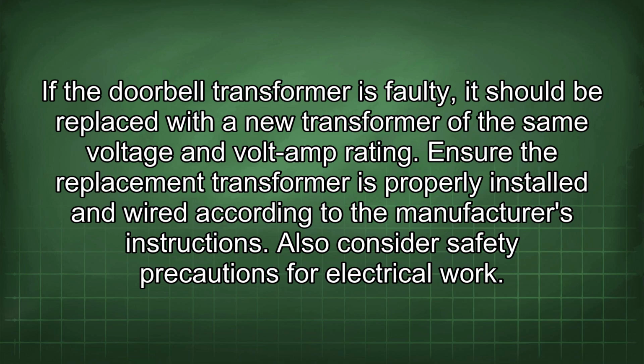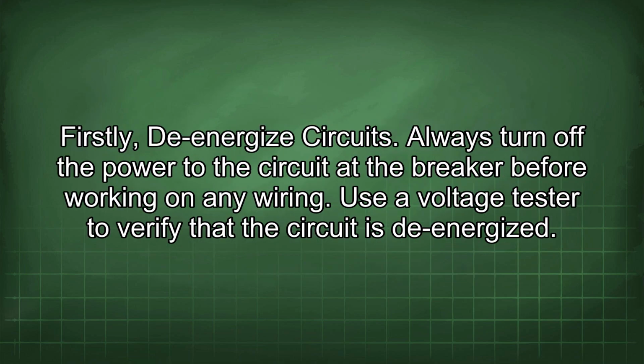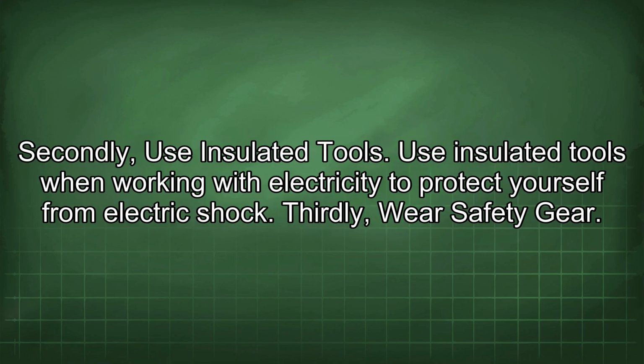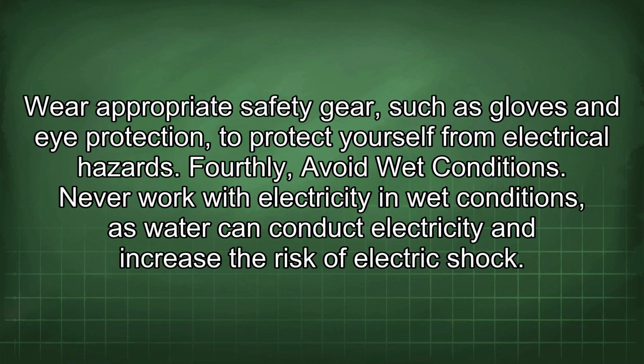Also consider safety precautions for electrical work. Firstly, de-energize circuits. Always turn off the power to the circuit at the breaker before working on any wiring. Use a voltage tester to verify that the circuit is de-energized. Secondly, use insulated tools. Use insulated tools when working with electricity to protect yourself from electric shock. Thirdly, wear safety gear. Wear appropriate safety gear, such as gloves and eye protection, to protect yourself from electrical hazards. Fourthly, avoid wet conditions. Never work with electricity in wet conditions, as water can conduct electricity and increase the risk of electric shock.